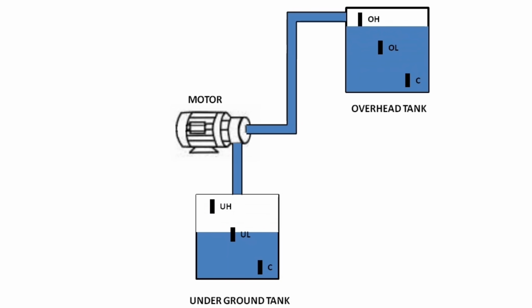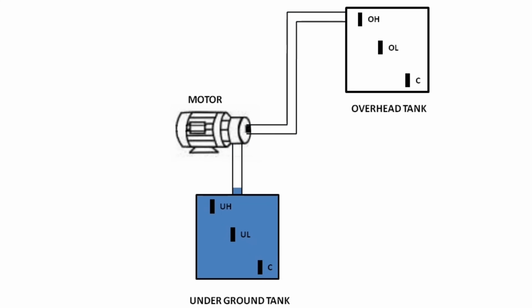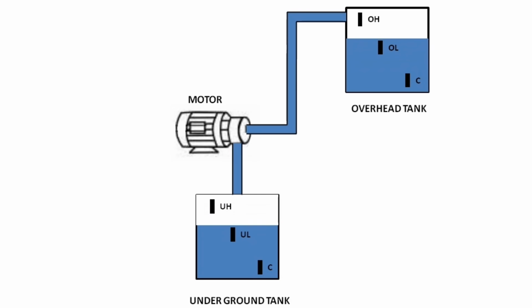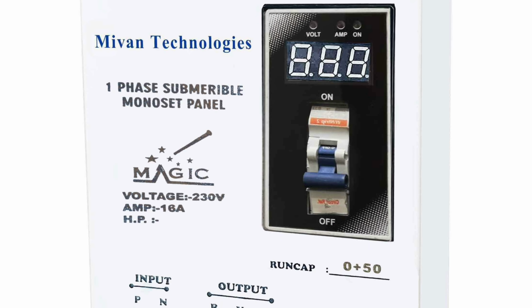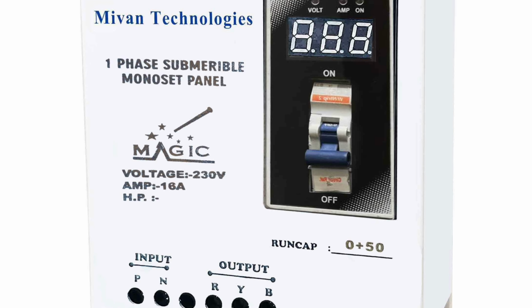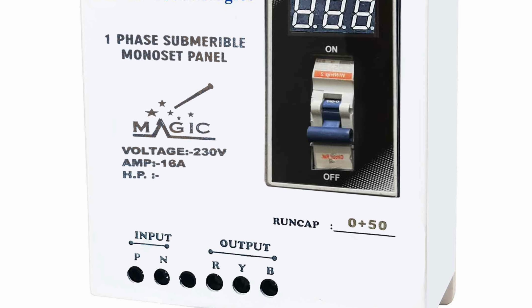You need to put 3 sensors in the overhead tank and 3 sensors in the underground tank. When the water level of the overhead tank becomes low, meaning the water goes down from the middle sensor, and water is present in the underground tank or sump, the motor starts automatically. The tank starts filling up. When the water level reaches the higher level, the motor automatically switches off. Auto off when the tank is full or the sump is empty. This model is also suitable for MCB starter panel and submersible motor.